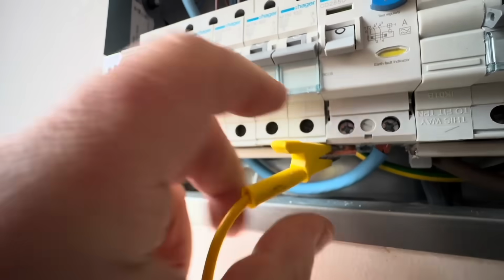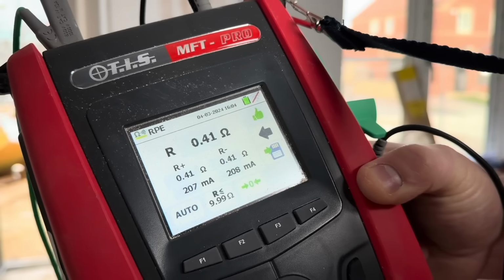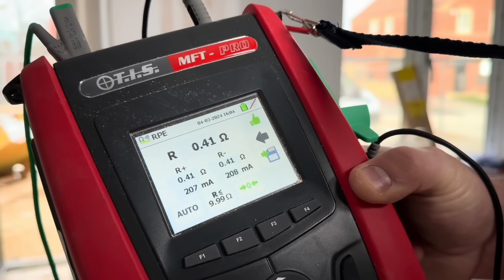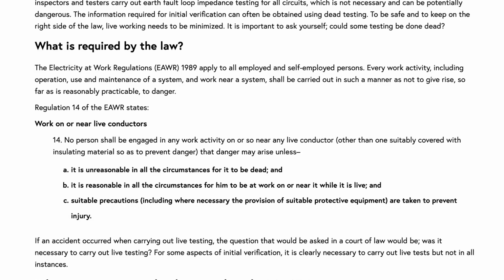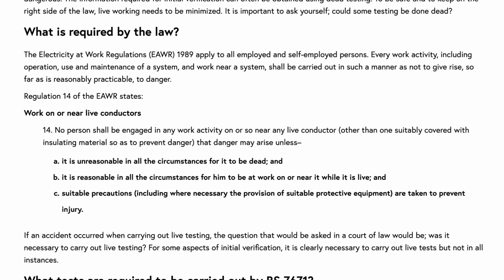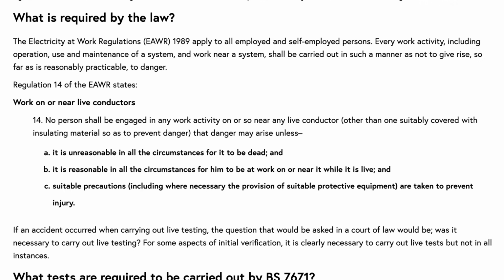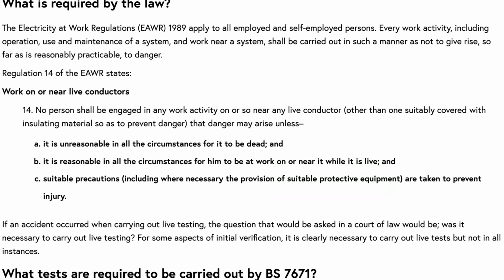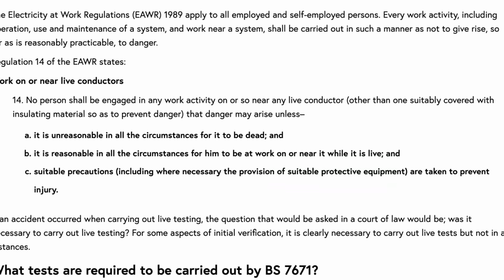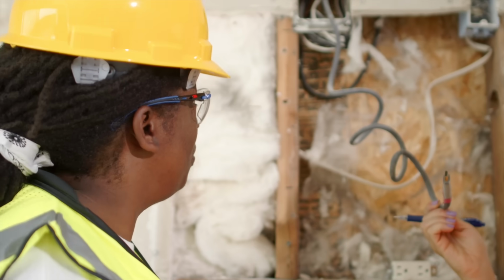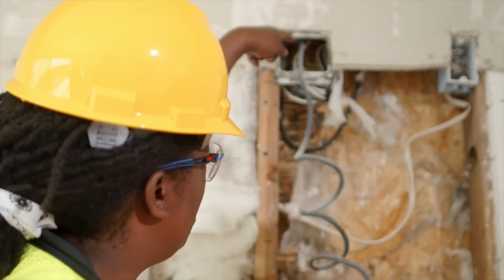Instead, the information can often be calculated by measuring the conductor resistances in a dead circuit. The organisation cites Regulation 14 of the Electricity at Work Regulations, which states that no work should be carried out on or near live conductors unless it is unreasonable for them to be dead. It says a risk assessment should be carried out to determine what live testing is needed, and where live testing is required, suitable precautions shall be used as set out by Regulation 14.